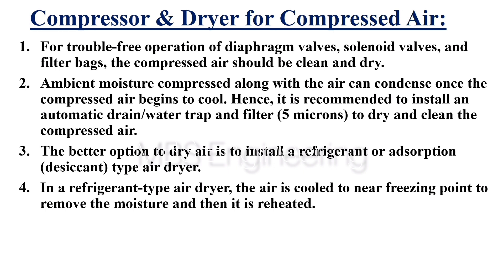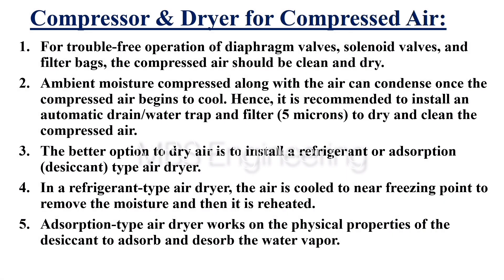Point 4: In a refrigerant type air dryer, the air is cooled to near freezing point to remove the moisture and then it is reheated. Point 5: Adsorption type air dryer works on the physical properties of the desiccant to adsorb and desorb the water vapor.